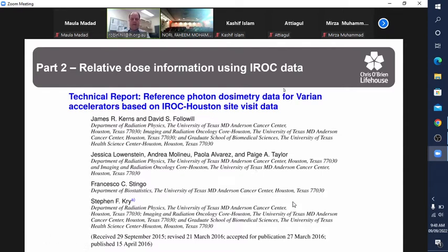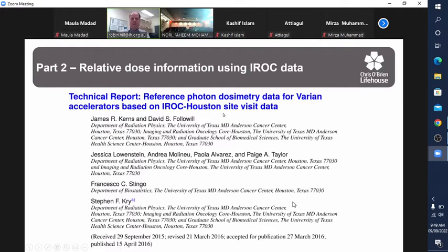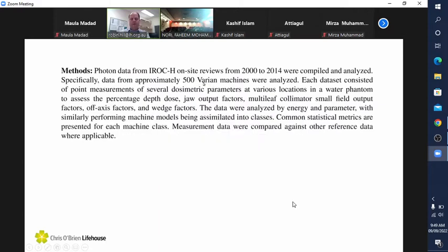The next paper, I think from Medical Physics, is publicly available. This was reference photon dosimetry data for Varian linacs. They've taken data from 500 Varian machines and they've got a whole range of factors: depth doses, output factors, multi-leaf collimator small field factors, off-axis and wedge factors.